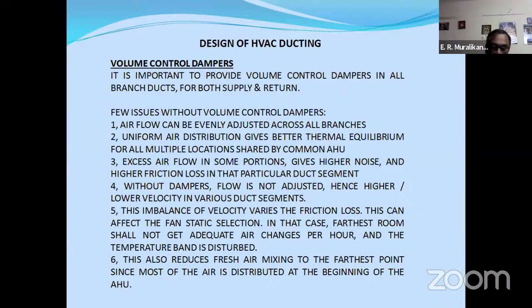There will not be proper air balancing, and thermal equilibrium will be disturbed terribly. One more thing: the first room will get very good fresh air because it comes at the first point, and the farthest room will get less fresh air. So all these things are there. People may say, I save 5 rupees or 10 rupees on this damper, but actually we are not supposed to do that. We have to put volume control dampers for all duct branches.